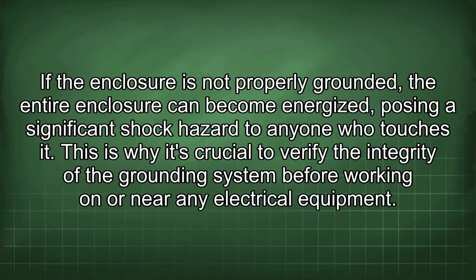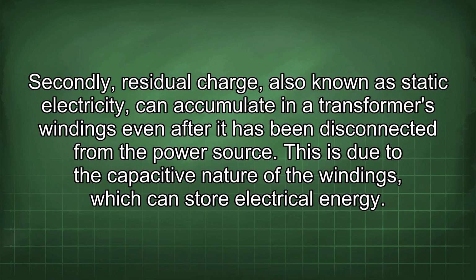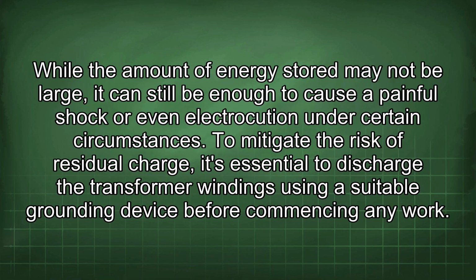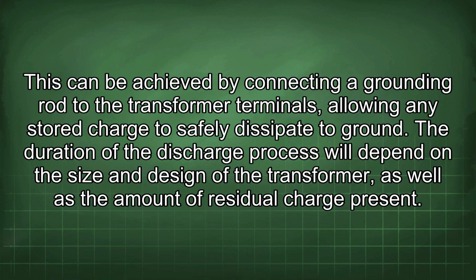Secondly, residual charge, also known as static electricity, can accumulate in a transformer's windings even after it has been disconnected from the power source. This is due to the capacitive nature of the windings, which can store electrical energy. While the amount of energy stored may not be large, it can still be enough to cause a painful shock or even electrocution under certain circumstances. To mitigate the risk of residual charge, it's essential to discharge the transformer windings using a suitable grounding device before commencing any work. This can be achieved by connecting a grounding rod to the transformer terminals, allowing any stored charge to safely dissipate to ground. The duration of the discharge process will depend on the size and design of the transformer, as well as the amount of residual charge present.